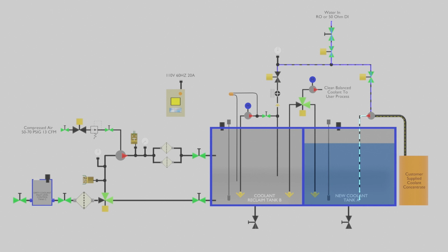Once Tank A reaches its pre-programmed level, the incoming Tank A water supply solenoid shuts off until the level drops sufficiently after providing a 24/7 on-demand supply of new coolant to the customer's process.